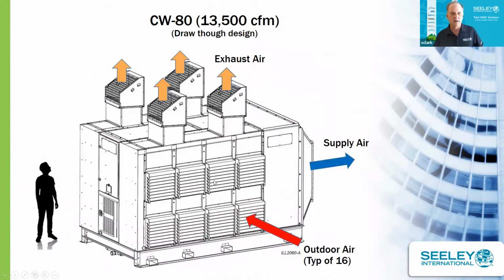If we look at our large units that are made in Australia, our CW80 units, with 13,500 CFM of delivered supply air to the space, these units are really an industrial, bulletproof unit. They're about the size of a shipping container. You can see the silhouette of a person standing there to give you a sense of the size of the unit. It has 16 of these cores, these heat exchangers. The outdoor air enters into this stainless steel louver. Behind that is a MERV 8 filter.